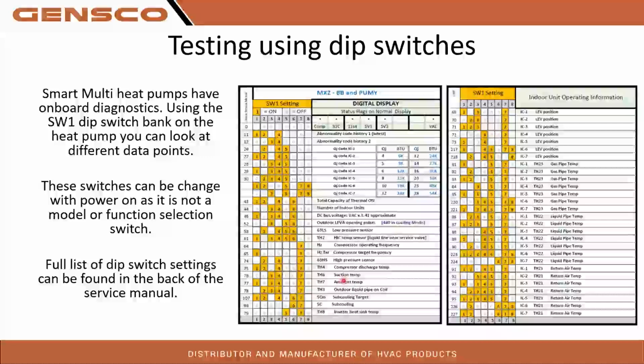Another one I'll look at quite commonly is if I suspect systems are crosswired, like port A is wired to port B, or head A is wired to port B. I can see it using dip switches as well. If somebody tells me, hey, I got a 6, a 9, a 12, and a 15 on ports A, B, C, D, I can come over, use these dip switches, and see what head is connected to which port. The weird thing about it is it's going to give you a QJ code. So if it's a 6K head, it's going to say 4, but it translates over to 6. If it's a 9K, it'll be 5, and so on, like you see in the chart here.